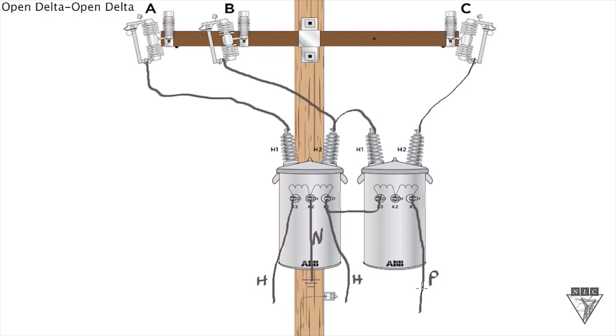Just make sure that you do not hook the power leg up to the house because then you'll send too much voltage into the home. You only want to use the two hot legs in the neutral for the house and then you can utilize all three legs for the three phase load.